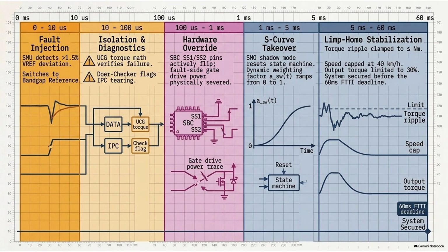And it reacts in just 10 microseconds? 10 microseconds is effectively instantaneous in mechanical terms. When the SMU detects that tiny voltage ripple, it immediately isolates the healthy motor's critical data channels, cutting them off from the bad ground and switching their power supply over to a backup, heavily shielded source called a band gap reference.